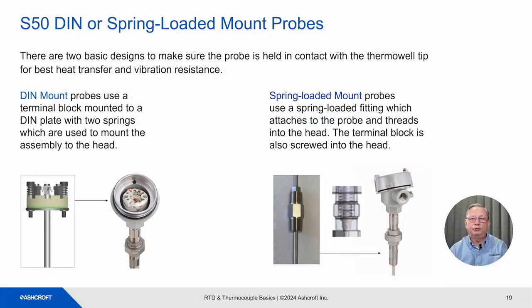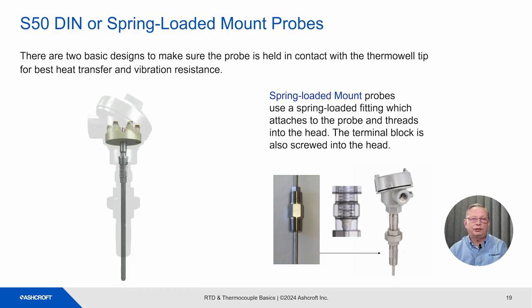Spring-loaded mount probes use a spring-loaded fitting, which attaches to the probe and threads into the head. The terminal block is also screwed into the head. When inserted into a thermowell, the spring in the fitting will hold the probe against the tip.